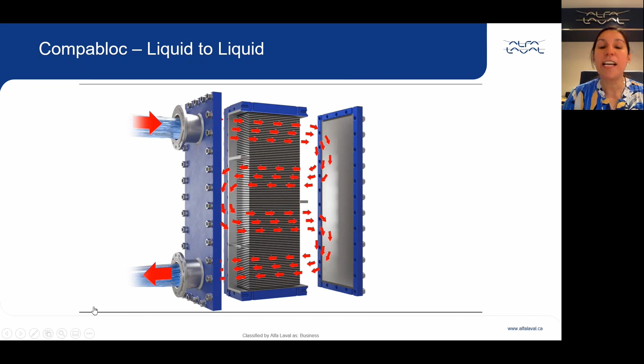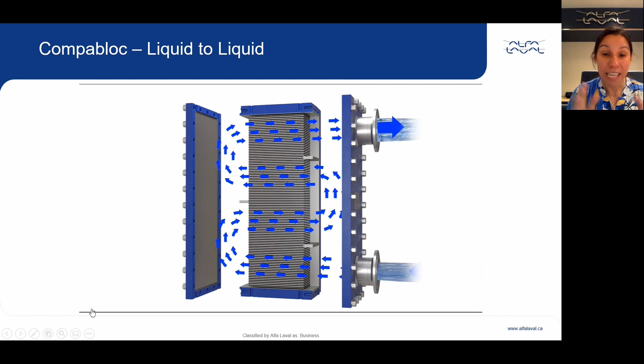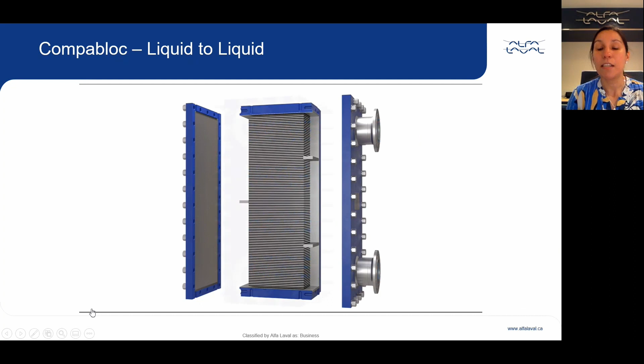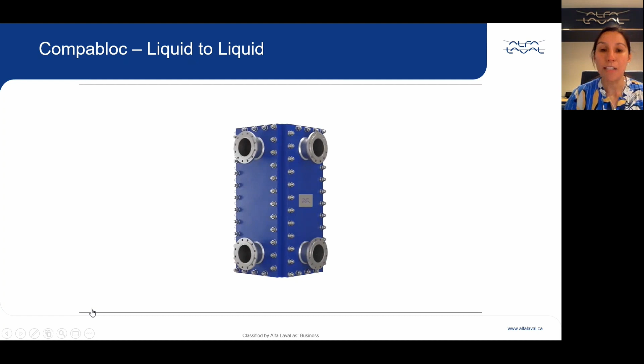Now you can say shell and tubes can be designed with multi-pass configuration too. Yes, probably you can add multiple passes on the shell. However, in the Compabloc, you can add multiple passes on both sides. So you can really adapt the same heat transfer area to multiple demands in thermal performance by adding or removing pass plates to match the thermal performance required. Now you will say, Monica, but adding pass plates is also reducing the cross-section area of the heat transfer for the fluid. So it will also increase the pressure drop. Yes. And how do you balance that? Well, that's the reason why I have a job. There must be a balance between thermal efficiency and pressure drop, and that's what we strive to achieve when we design a Compabloc heat exchanger.